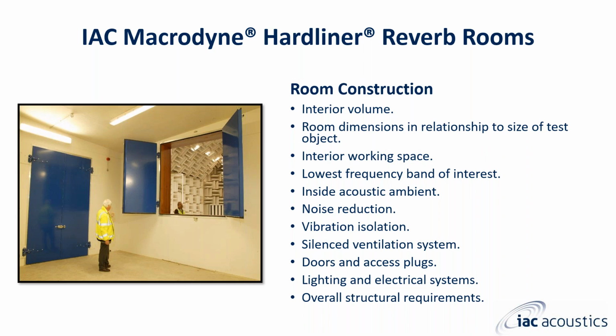So we'll consider the size and types of doors and lighting and climate controls appropriate to the work intended. And this is all done in a modular format. All these elements are assembled with an engineered modular structural framework that ensures the overall integrity of the reverberation room. With the IAC Moduline component system, virtually any size room can be created.